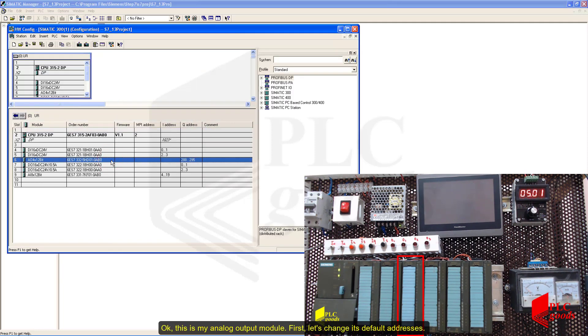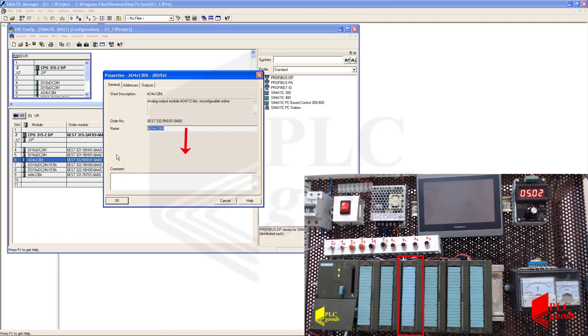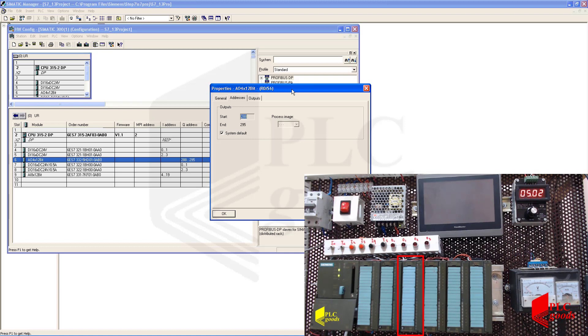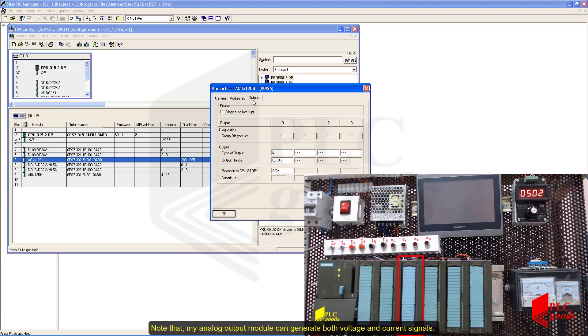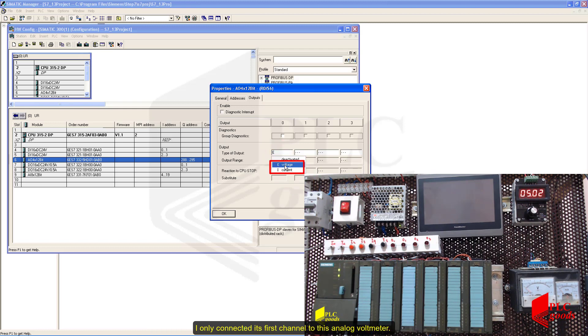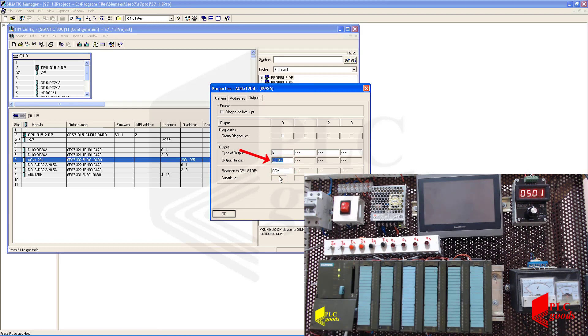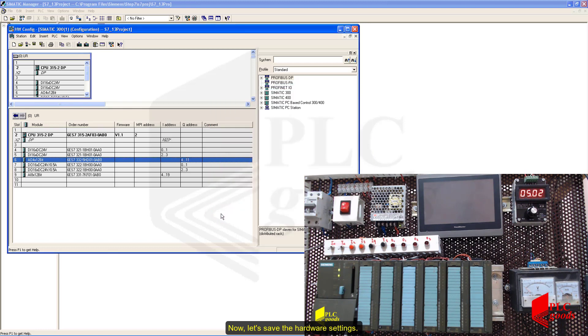This is my analog output module. First, let's change its default addresses. Note that my analog output module can generate both voltage and current signals. I only connected its first channel to this analog voltmeter. So let's select the voltage item and then an appropriate range: 0 to 10 volts. Now let's save the hardware settings.